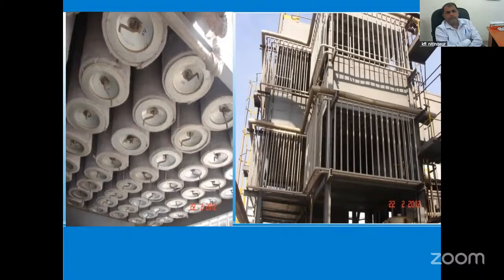As and when we clean the filter and do not succeed in achieving the DP below 75 mmWC, then replace all the filters with new ones.